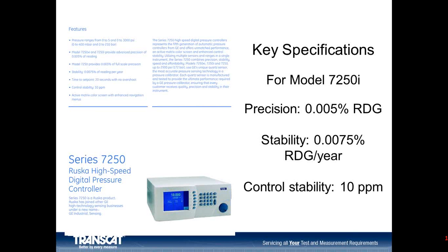So how do we find the parameters? One place to look is the specifications from the manufacturer. Sometimes they're pretty straightforward. Other times you have to dig a little bit. But here's an example for a digital pressure calibrator, somewhat like in the example I made earlier.